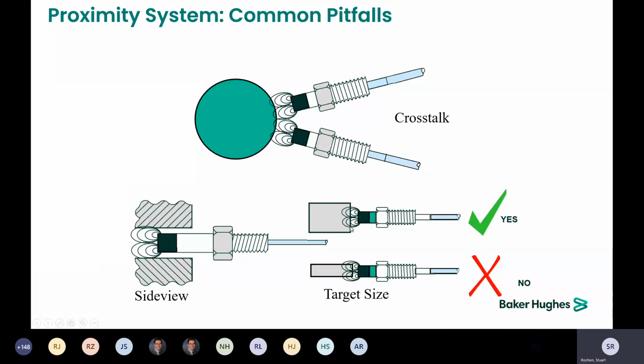If the radio field is wrapping around the sides, it will not read accurately. So we have a minimum shaft diameter and also a minimum flat target size. You do also need to make sure that that flat target is available all the way around the circumference.